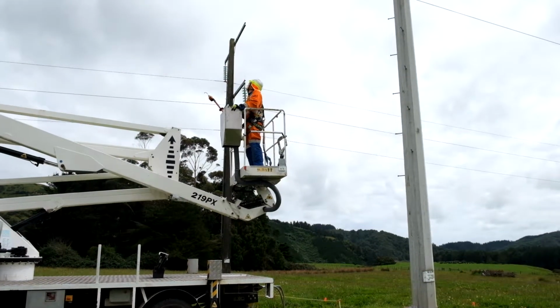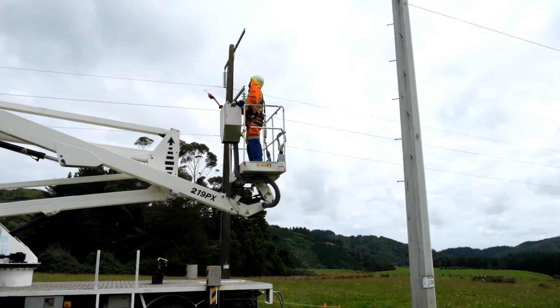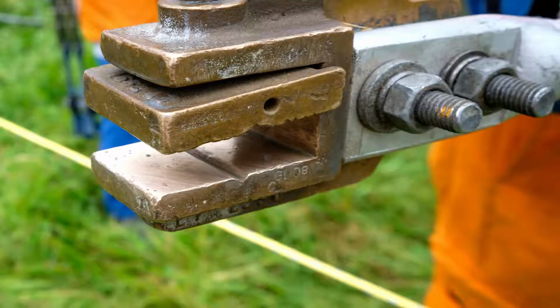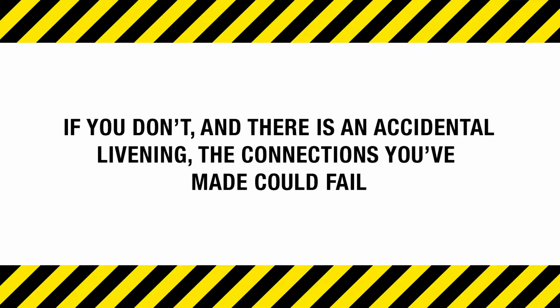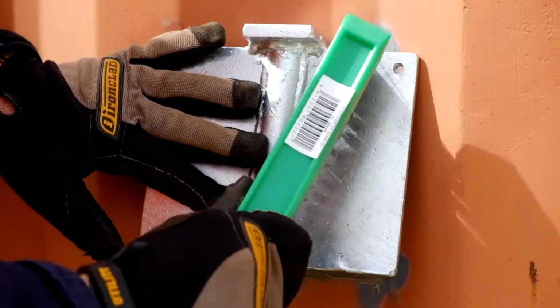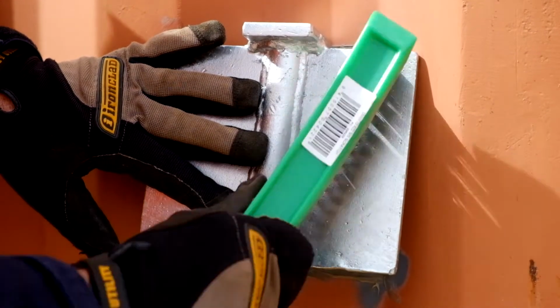When you get to a site, it's essential that when you're inspecting your earthing and bonding equipment, you also ensure that all the contact surfaces are clean, so that the equipment can do its job properly. If you don't, and there's an accidental livening, the connections you've made could fail. You could get badly hurt, or worse. Let's start with looking at the earthed end connections.